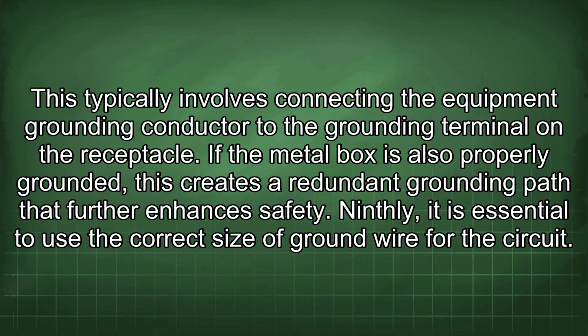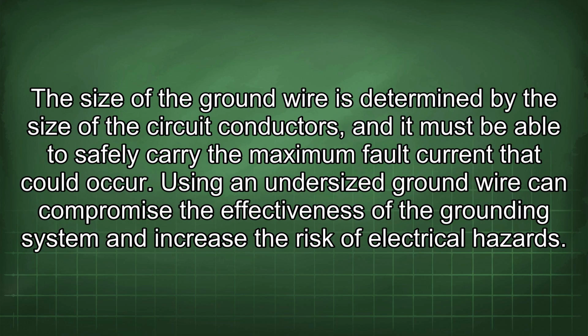Ninthly, it is essential to use the correct size of ground wire for the circuit. The size of the ground wire is determined by the size of the circuit conductors, and it must be able to safely carry the maximum fault current that could occur. Using an undersized ground wire can compromise the effectiveness of the grounding system and increase the risk of electrical hazards.